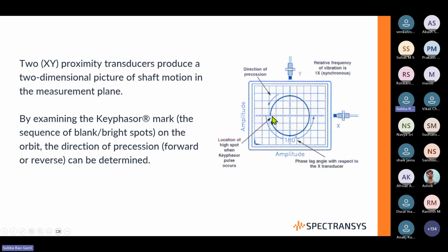So when the Keyphasor is going negative, when the Keyphasor is firing, you'll have the blank, and when the Keyphasor is closing up, you have the bright spot. So the event starts with the Keyphasor blank and then the bright. This is the way in which the shaft center is moving, so the whirling movement of the rotor is in this fashion.